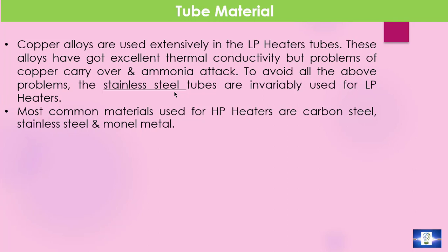Stainless steel is unaffected at all operating conditions except that it is susceptible to chloride induced stress corrosion. The most common materials used for HP heaters are carbon steel, stainless steel, monel metal, etc.